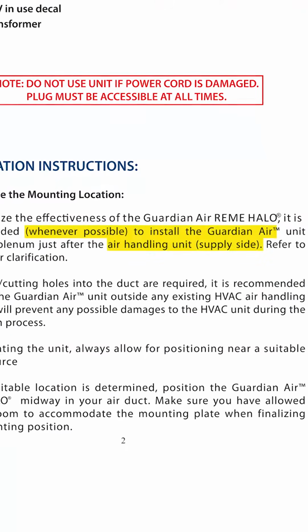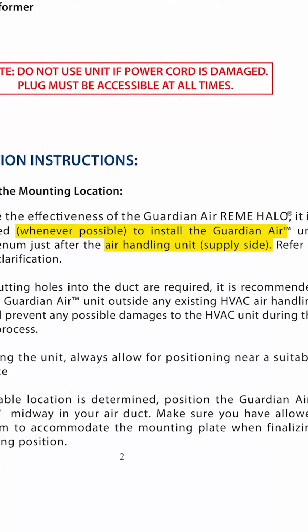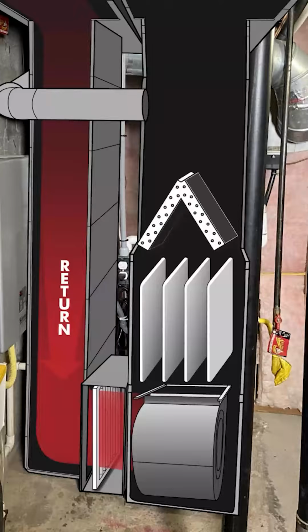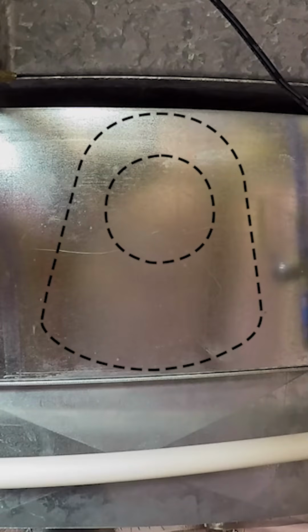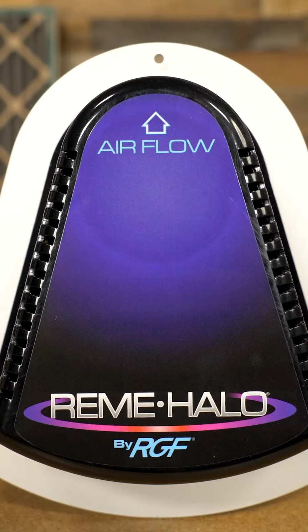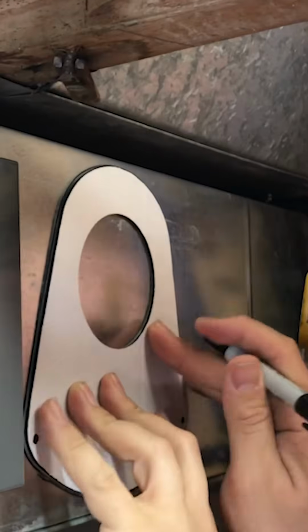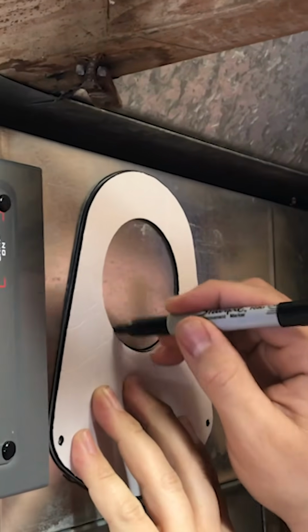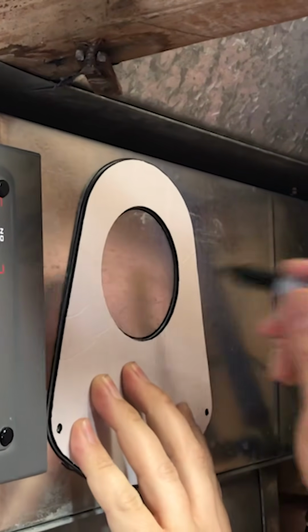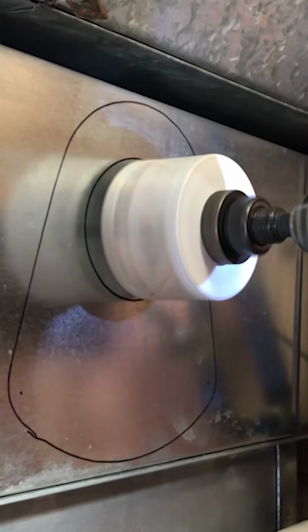It's recommended whenever possible to install on the supply plenum just after the air handler. So determine which side is the supply and identify where you'll have enough room to accommodate for the mounting plate, and pay attention to the airflow direction arrow. Once you determine where you're going to place the unit, you can use the center of the mounting gasket as your template. Trace the outline, then make your cut.